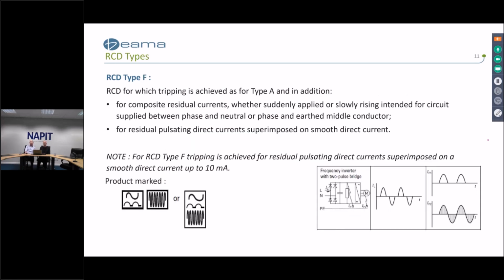Okay, so the next one is Type F, and this is a relatively new product. Type AC and Type A have been around for some years, even decades, but Type F is relatively new. And this is to respond to the ever-increasing complexity of control systems. Type F RCDs will respond to the same residual currents as Type AC and Type A, but will also respond to composite residual currents of 10 Hertz, 50 Hertz, and 1 kilohertz. And this is really to accommodate complex currents, complex waveforms that are produced by some types of equipment.